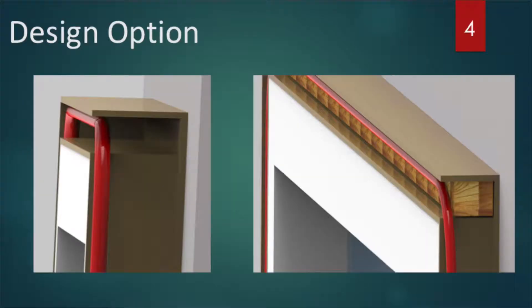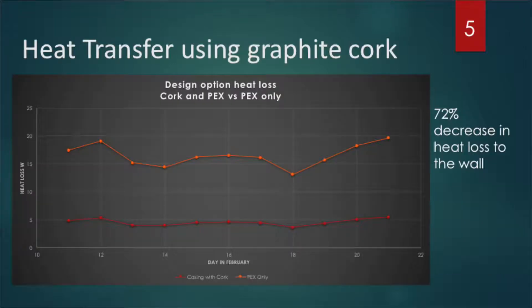The figure to the left illustrates the current design. To the right, we have added cork insulation to direct the heat to the window frame, to further increase the overall temperature of the window and increase thermal comfort. Adding cork to the space decreases the heat loss to the wall by 72 percent.